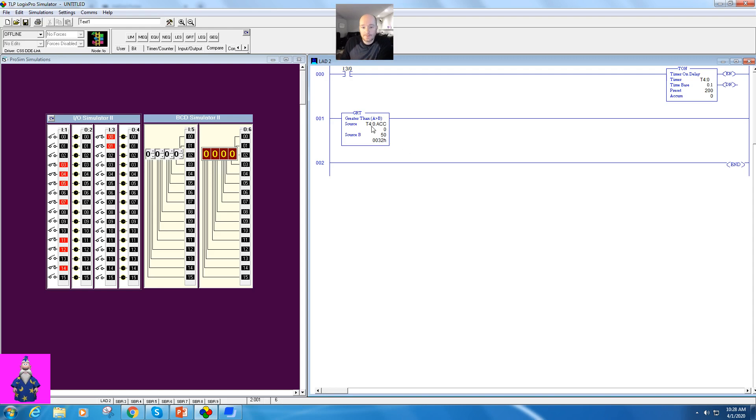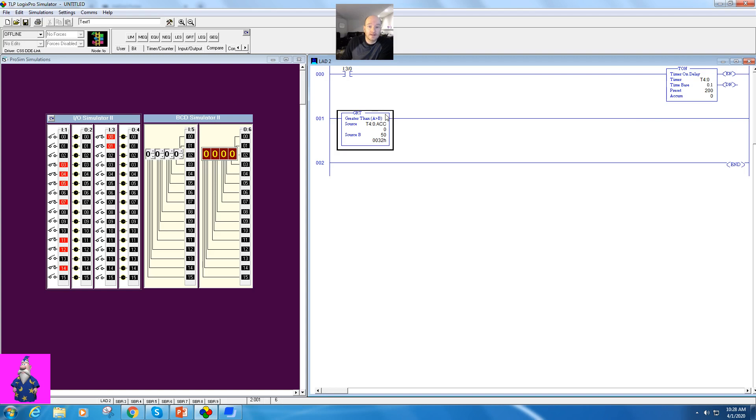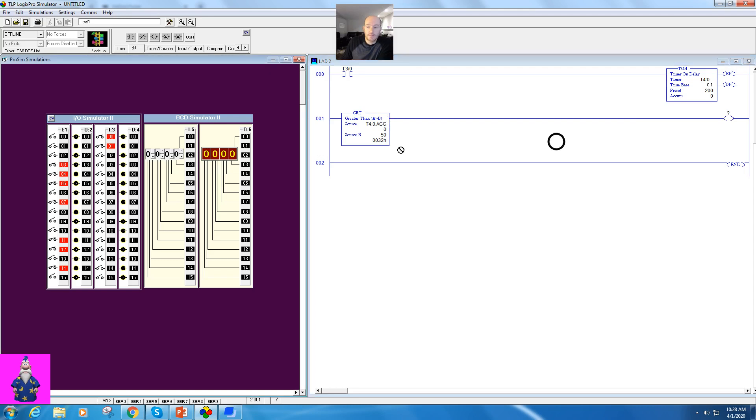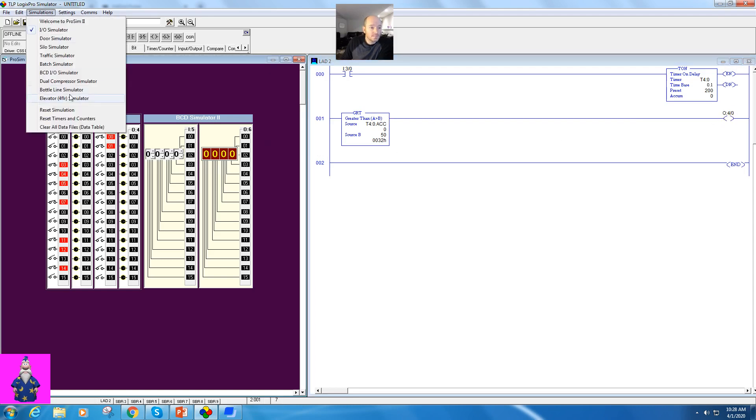Now watch what happens here. So this is T4 ACC, here's my preset value. When my accumulated is greater than 50, it will activate an output. I'll just make it this output right here.